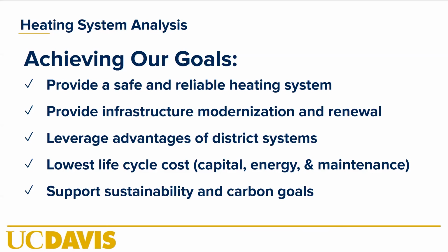So trying to marry the two up didn't work well, because when we need more heat, with either solar thermal or heat recovery, is in the winter, and they both make the most heat in the summer. With solar thermal, the main challenge was there's a big expense to put in all the solar thermal farm, this bunch of panels that are going to cost a lot. And if we're going to size it in a way that's going to actually serve the needs of the winter, then we're going to have too much in the summer.